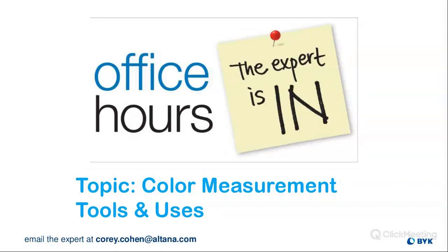And so we have a few different light booths. We have some standard light booths that have different light sources: tungsten, fluorescent light sources, daylight. And so that can help with metamerism. Metamerism, real quick, is just when a standard and sample may match under one light source but not under another. So it may be difficult for you to understand what's going on just by looking at the numbers in the instrument. And it can be good to have a light booth on hand as a companion to your spectrophotometer that can let you see what's going on actually.